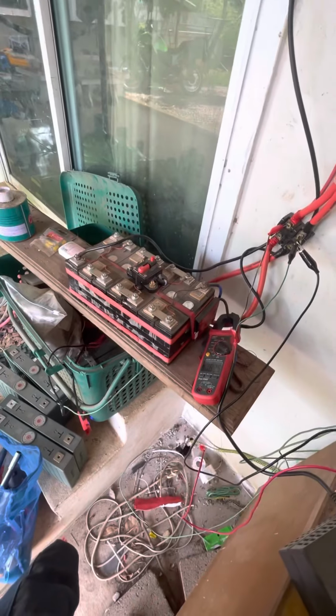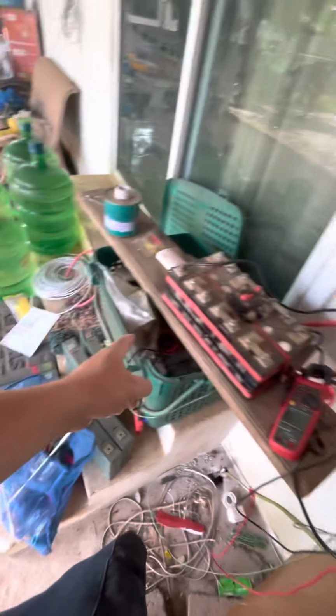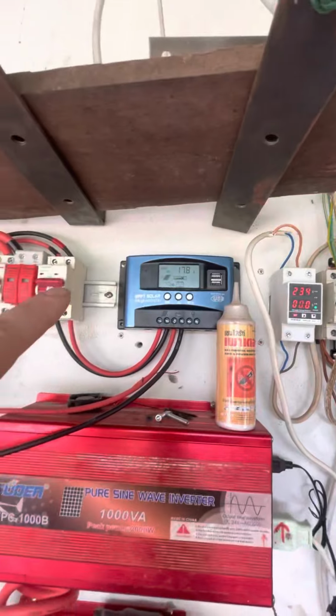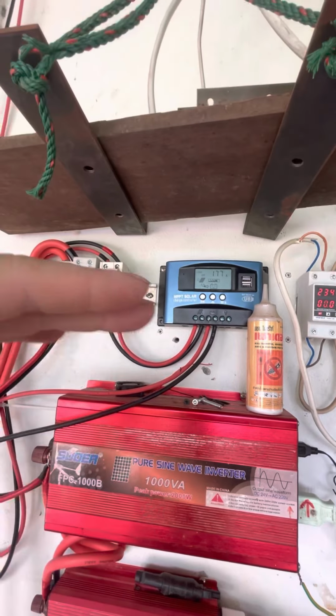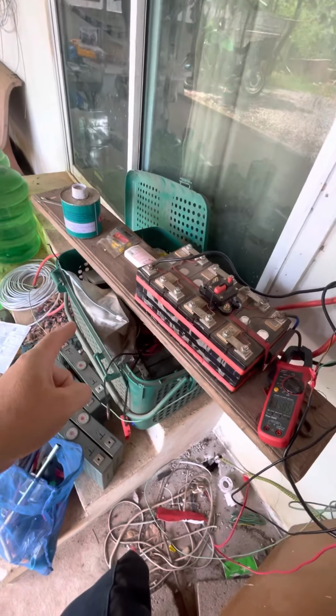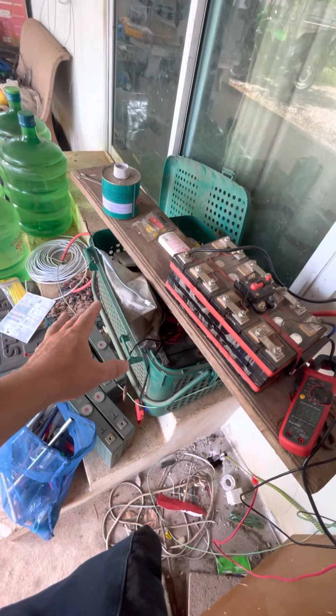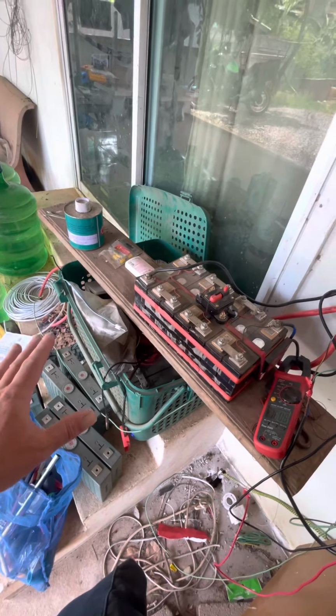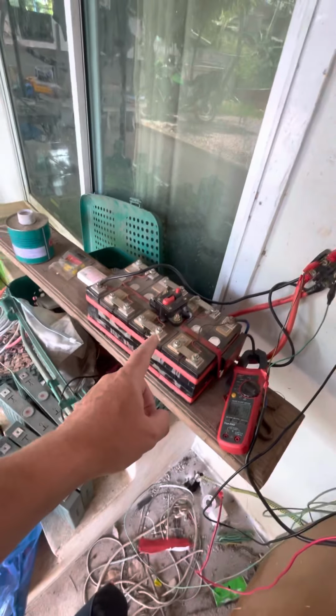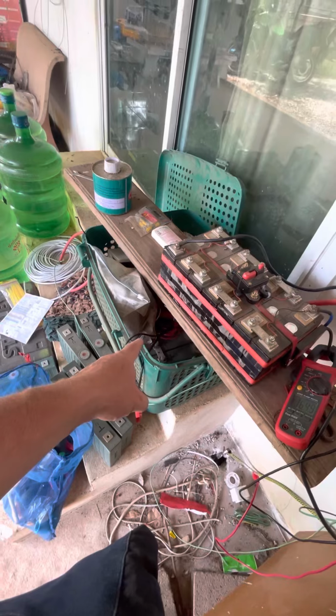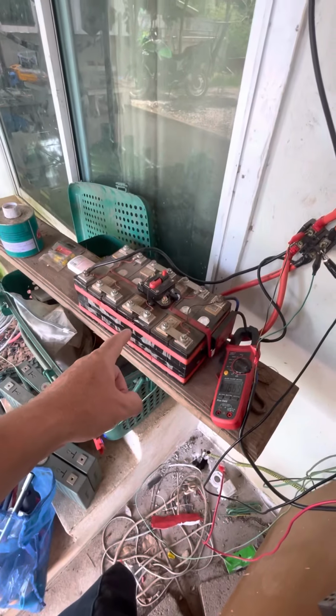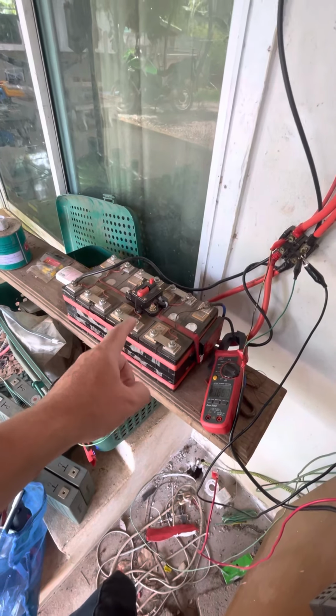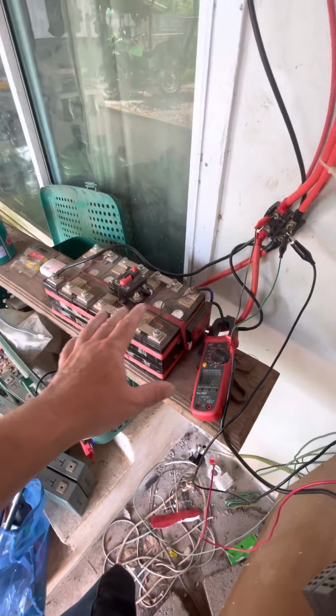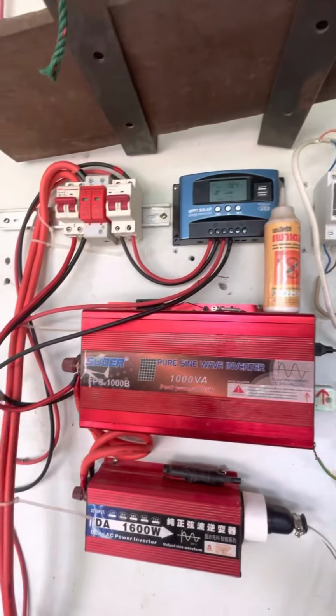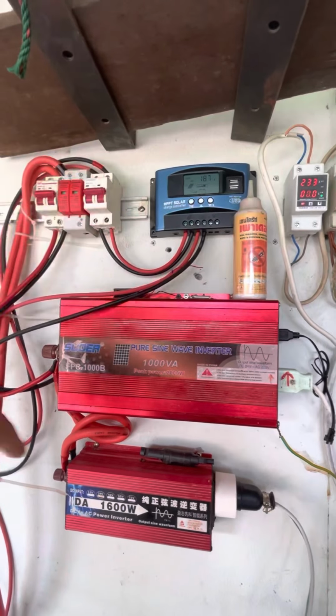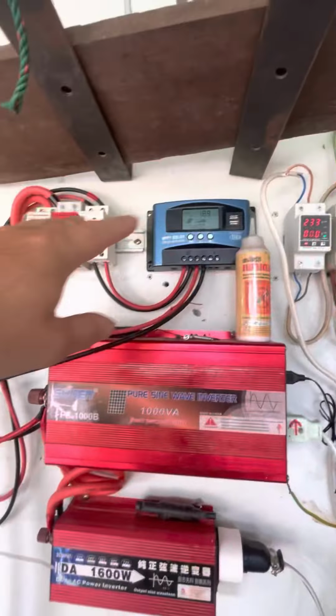So I thought, I wonder, is it that this one's shut down because I've got this controller set on 29.2 volts - the highest volts I want - that charges that battery. And then what happens - I've got this one, the BMS just shuts down at 28.2, and it's perfect, it works great. I thought, has the BMS - so what can happen sometimes is, if that's shut down because it's charged, it's got to 28.2 - if the BMS, for any reason, shuts down on this, the voltage coming in has got nowhere to go, and you end up getting this really high, crazy, up and down voltage coming from the solar panels into this lot.